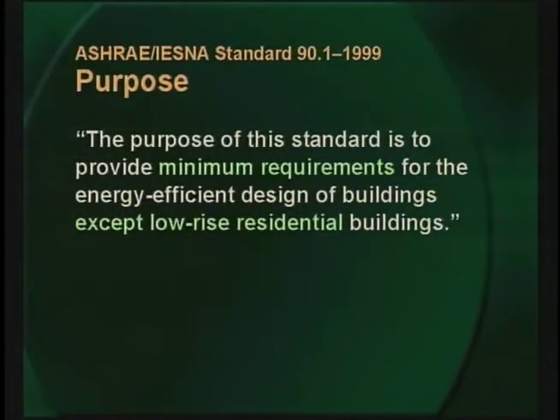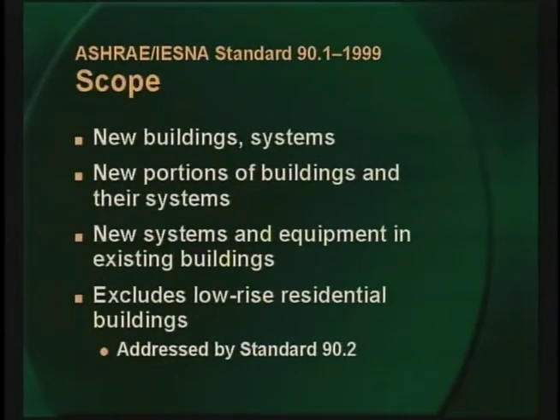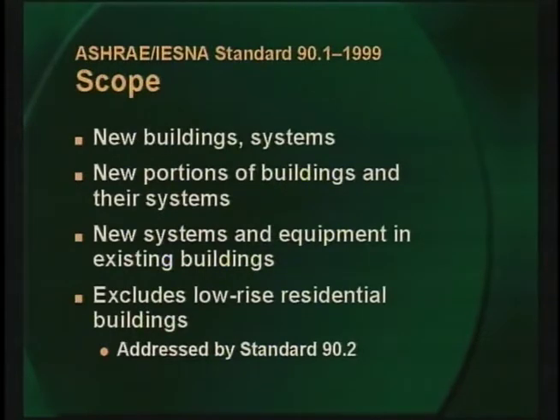The purpose of the standard is to provide minimum requirements, and it does not include low-rise residential dwellings such as family homes or duplexes. Its scope shows that it applies not only to new buildings, but also to additions and alterations. The mechanical section covers both mandatory and prescriptive requirements. Mandatory requirements include equipment efficiency, controls, documentation, labeling, and many other aspects of mechanical systems. Prescriptive requirements of Standard 90.1 include economizers, fan power limitations, hydronic system design and control, and related to today's subject, a simultaneous heating and cooling limitation.